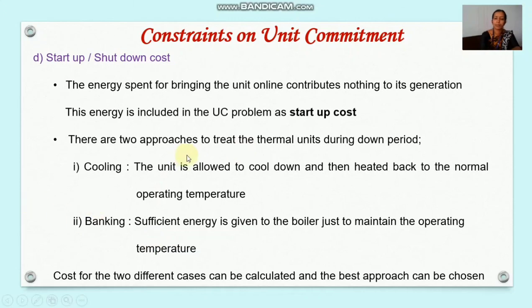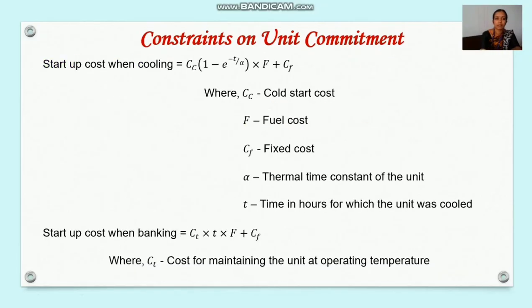So depending on the approach used for treating the thermal unit during its down period, we can calculate the startup cost. The equation for calculating the startup cost when the unit was cooled is Cc into 1 minus e raised to minus t by alpha, into F, plus Cf, where Cc is the cold start cost, that is the cost required for starting the unit from cold condition or ambient temperature condition.